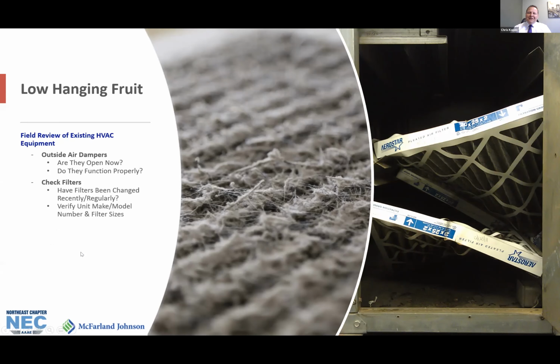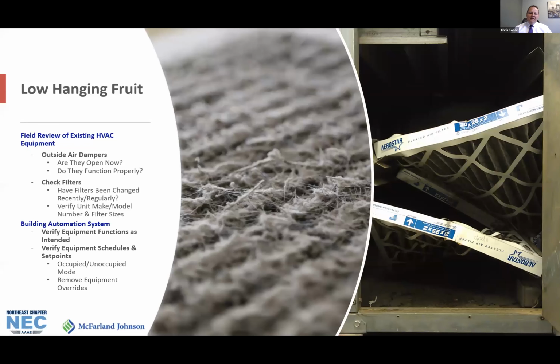Make sure your outside air dampers are open. Dampers or actuators can be loose or fail, and equipment schedules get adjusted or overridden. And you'd be surprised at how many times I've opened up an air handling unit to find the outside air dampers completely closed. As we talked about, update your HVAC filtration. Make sure your air handling systems are providing adequate airflow. There are no blockages, for example, a closed fire damper or smoke damper.